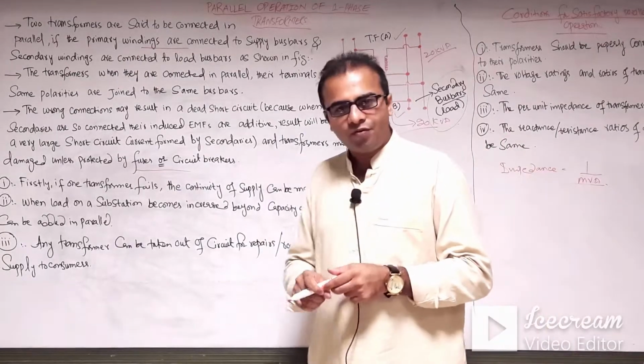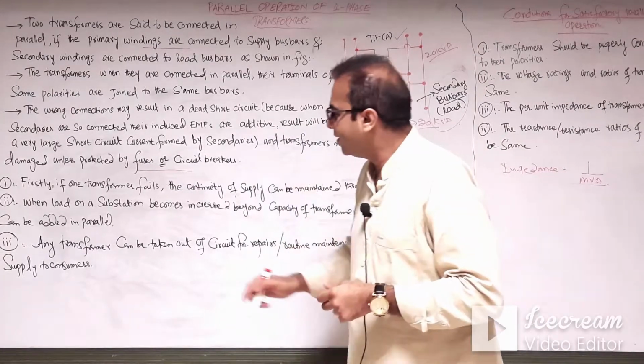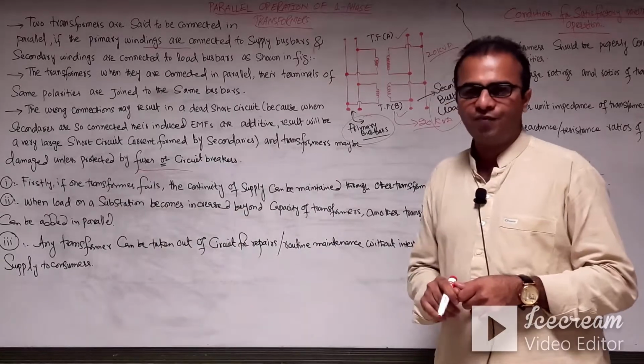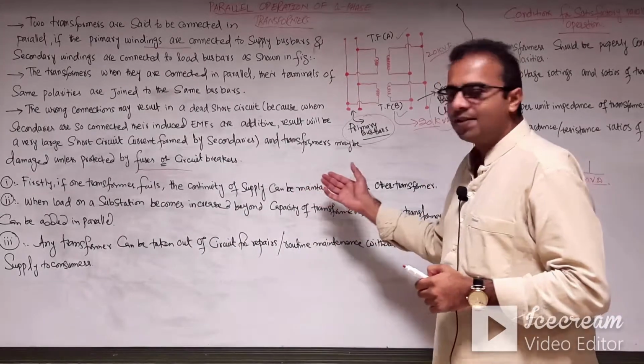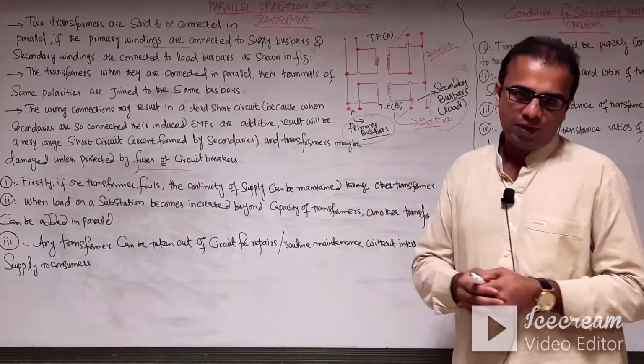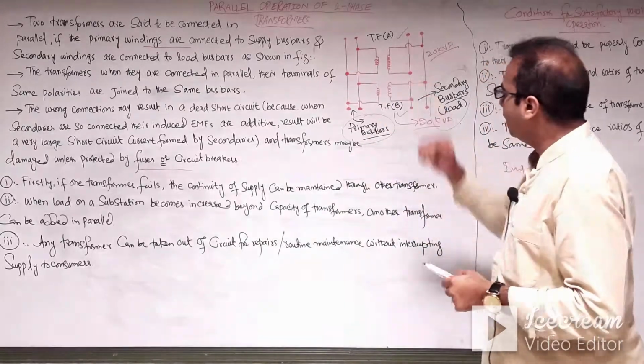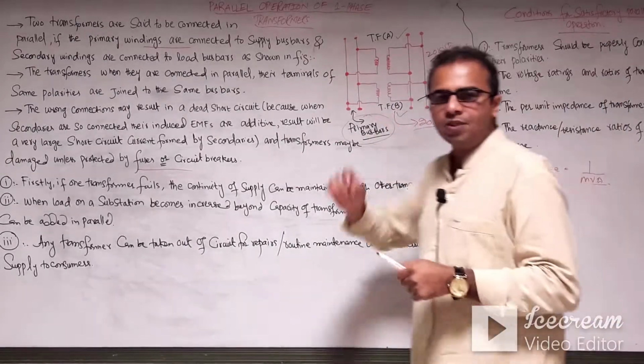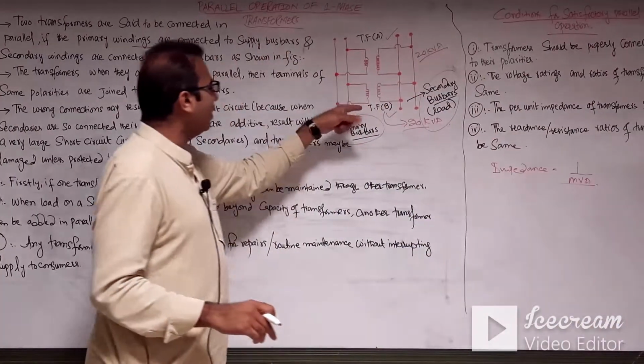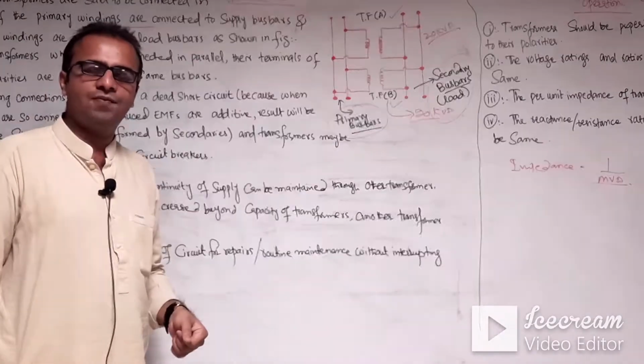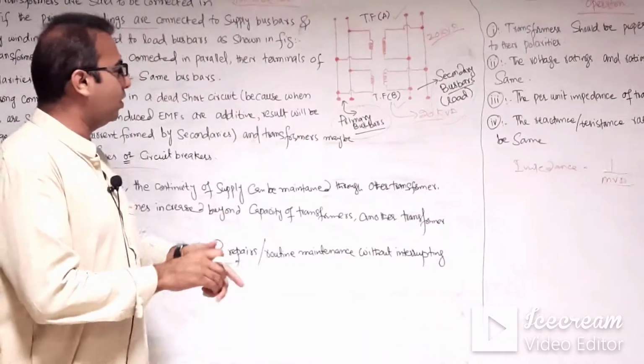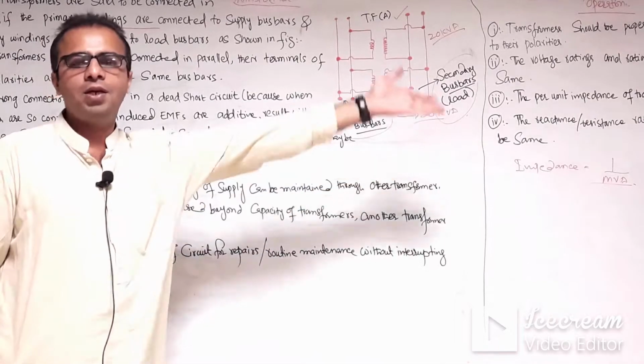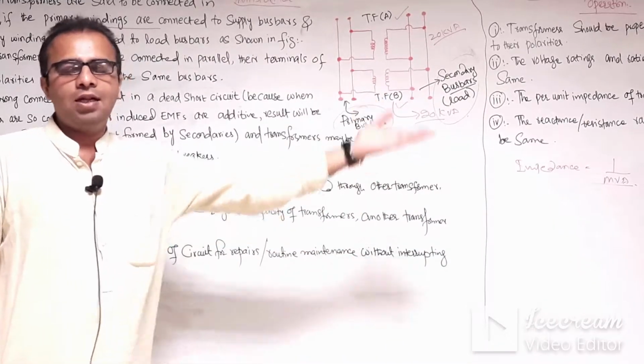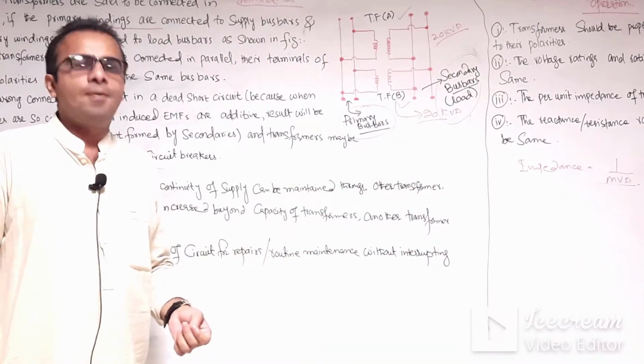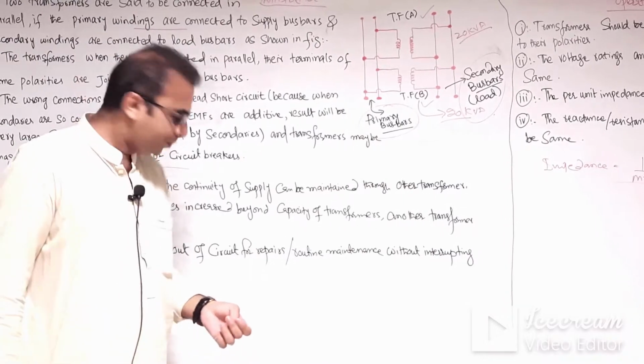The first advantage of the parallel operation of transformers is that if one transformer fails, the continuity of the supply can be maintained through the other transformer. Consider this figure. There are the two transformers A and B. If transformer A fails, the continuity of the supply can be maintained through transformer B. So this is another advantage of the parallel operation of the transformer.